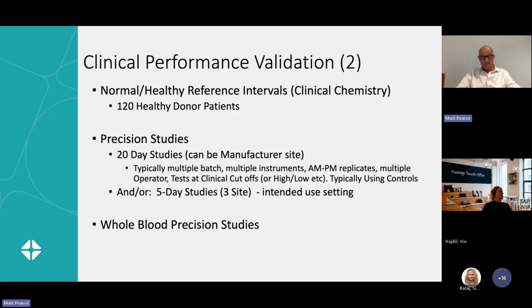In addition to the accuracy studies, which are the ones I've mentioned before, precision is also another main strand of labeling claims. And there are CLSI standards for dictating how these are set up. But basically, typically there's a 20-day study, and that includes multiple lots of cartridge of test, multiple instruments if you have instruments, morning and afternoon replicates, multiple operators, and then, depending on the kind of product, if there are different clinical cutoffs, you need to do the precision at those clinical cutoffs. You can also use control materials for a lot of these studies.